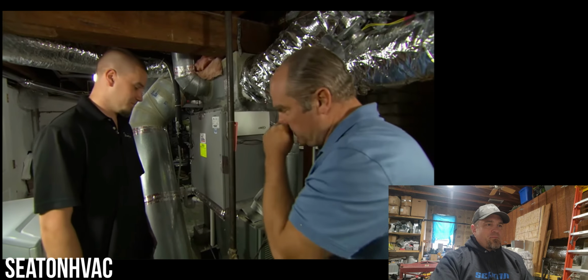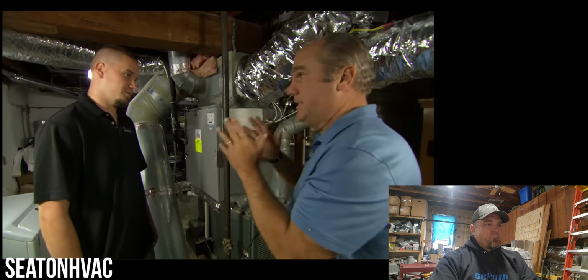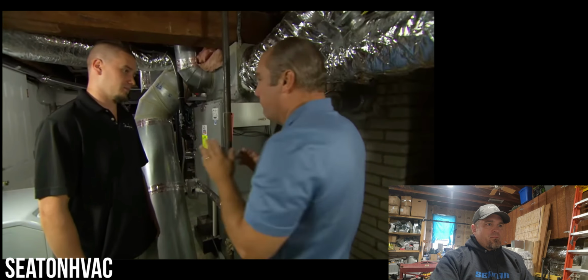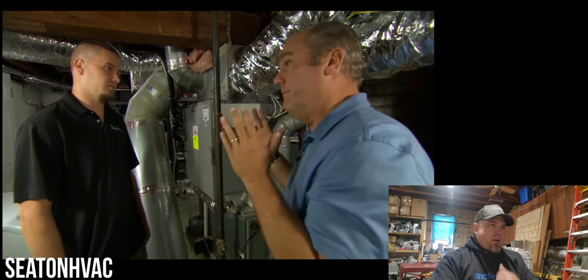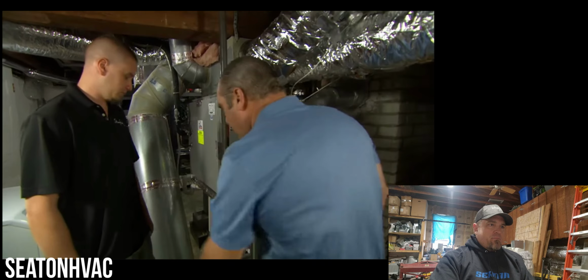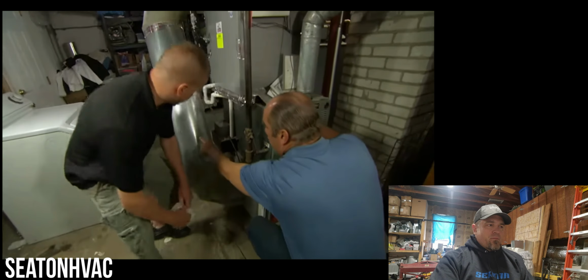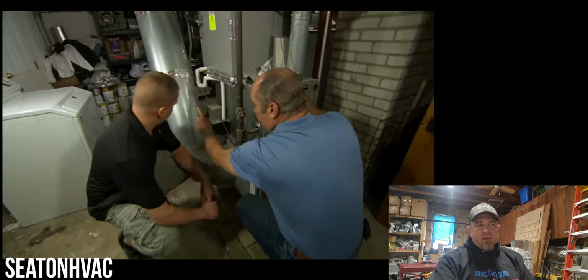All right. So anytime I hear about this condition, a frozen coil, first and foremost, I think about a lack of airflow through the unit. So here's the return air. So we're going to soon find out that it is the wrong size of air conditioner that they put in this house, but he should have addressed this ductwork first and as well after what he does here. So let's continue on.